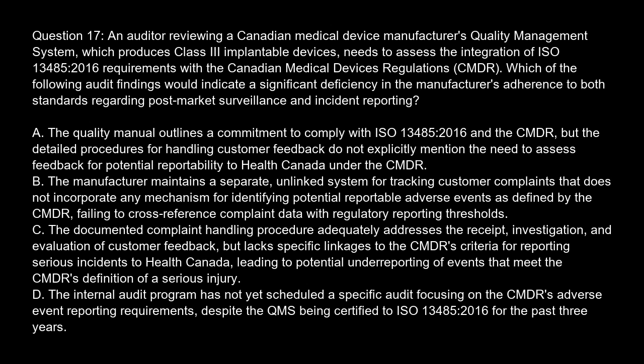Option C. The documented complaint handling procedure adequately addresses the receipt, investigation, and evaluation of customer feedback, but lacks specific linkages to the CMDR criteria for reporting serious incidents to Health Canada, leading to potential underreporting of events that meet the CMDR definition of a serious injury. Option D. The internal audit program has not yet scheduled a specific audit focusing on the CMDR adverse event reporting requirements, despite the QMS being certified to ISO 13485-2016 for the past 3 years.